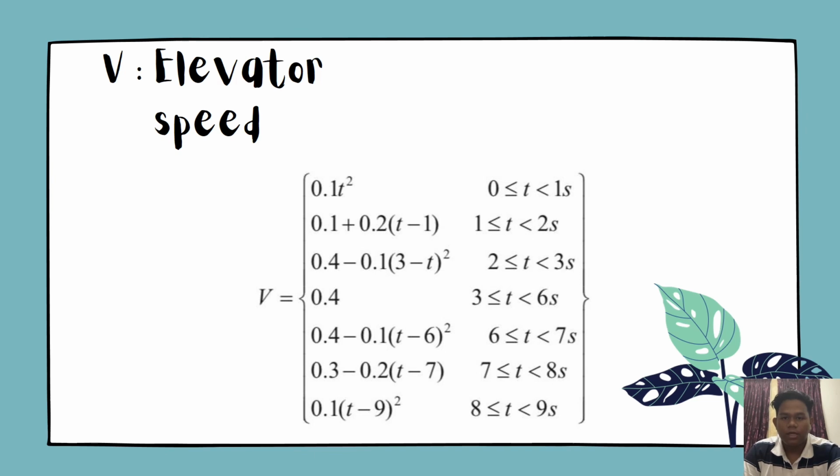Celerity and comfort are important qualities that an elevator should have. According to relevant regulations, its acceleration should be no more than 1.5 m/s² and its jerk should be no more than 1.3 m/s³ to ensure consistent performance during the startup and brake process.